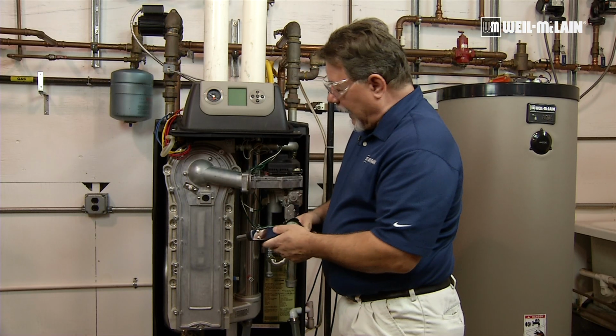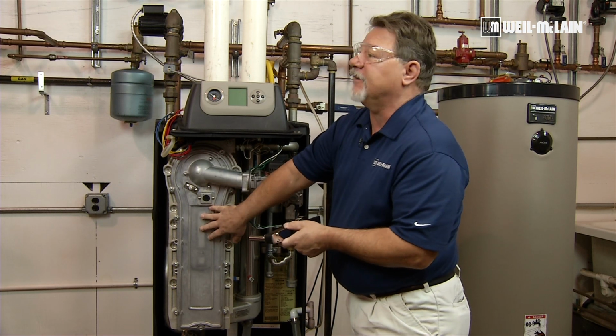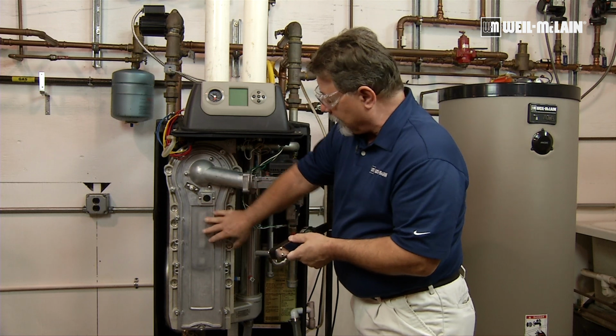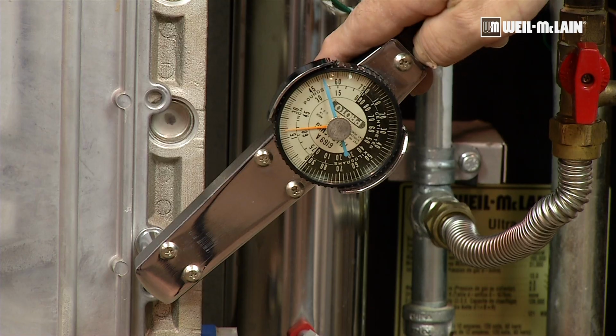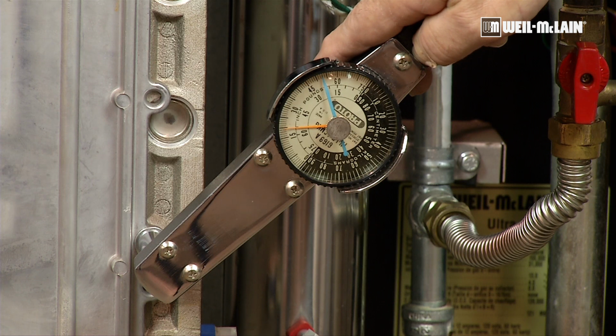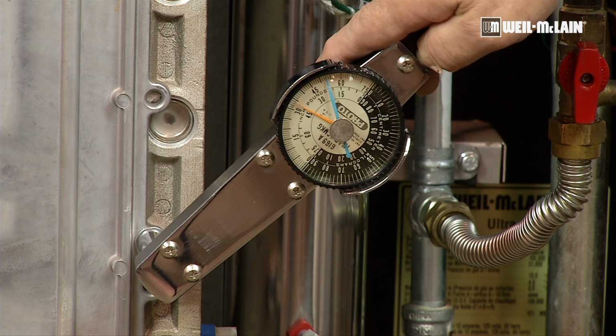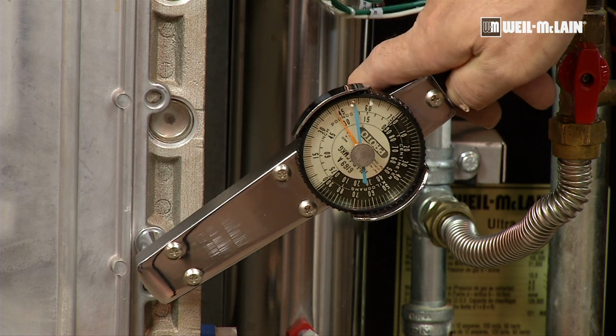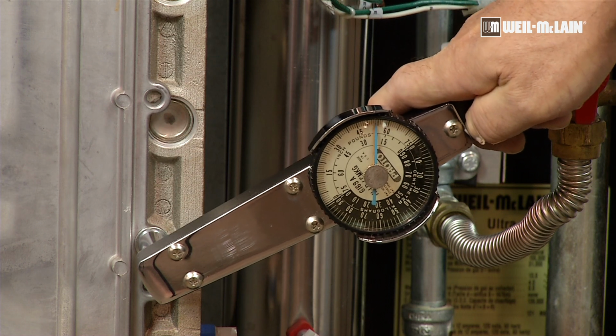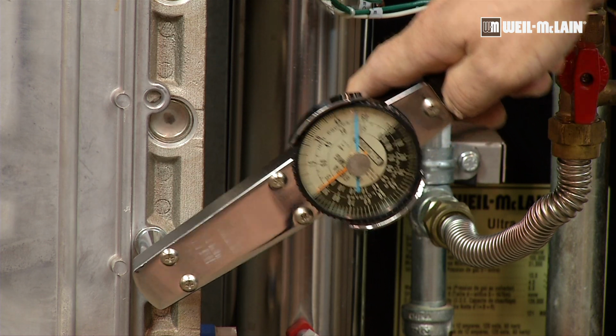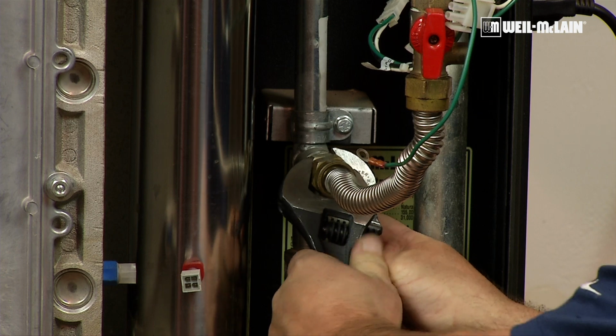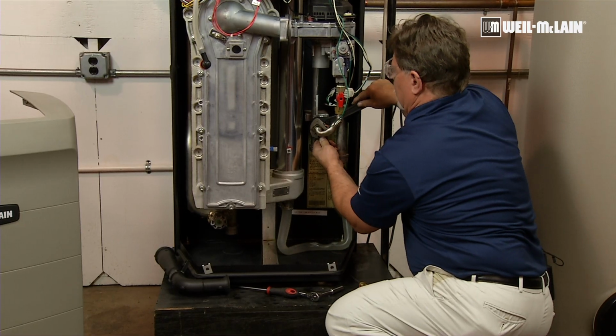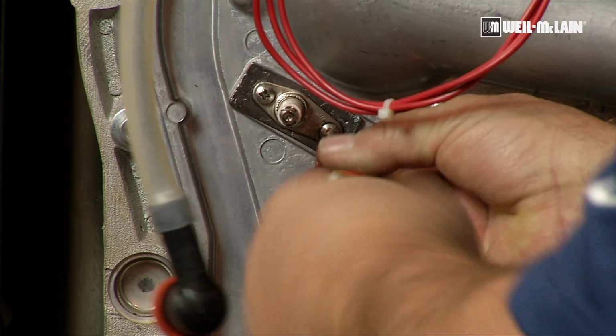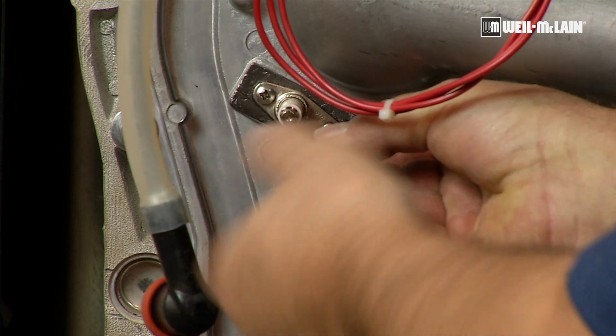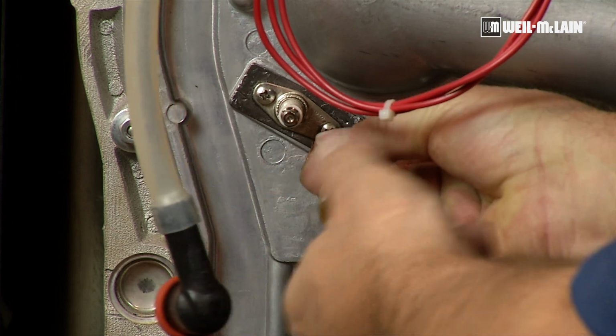So now we're on the last step of fastening the heat exchanger cover plate to the heat exchanger. Following the instructions in the manual, it says to set a torque of 50 to 60 inch-pounds on the nuts. After all the nuts have been tightened on the heat exchanger, we'll proceed to reattaching the gas line. So once the gas line has been reinstalled, it's time to reattach the wiring.